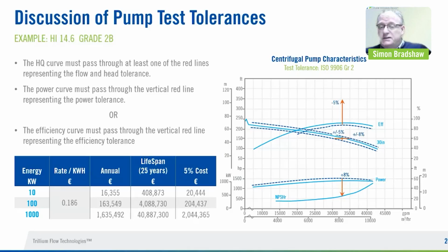Okay, so let's take some practical examples here. This one's, I won't say silly, but it's an example just to highlight a point. We're going to take an example of a pump where the purchaser specified HI 14.6 grade 2B, and what does that practically mean? Well, we've plotted it out here on the graphic on the right hand side. If we take each of these in turn, the head flow characteristic, the middle light blue line, has to pass through one of the red lines that correspond to the head and flow tolerance, which in this case is plus or minus 5% of head or plus or minus 8% of flow. So the two dotted lines either side of the head flow characteristic show you the extent to which that pump could vary on the test stand and still be acceptable.